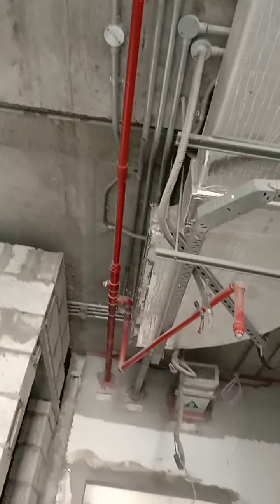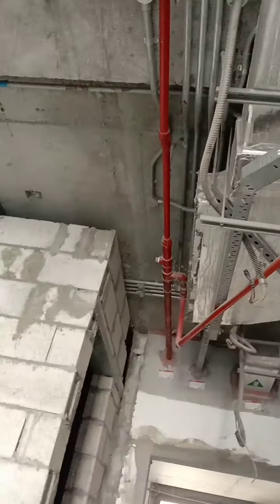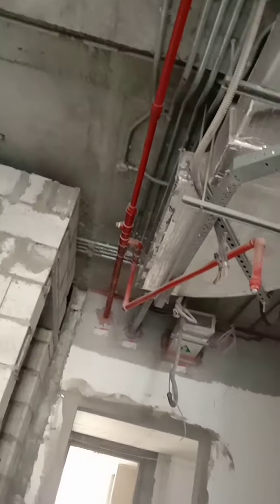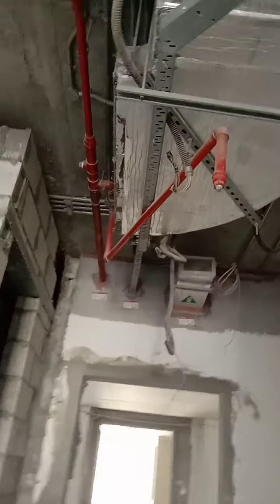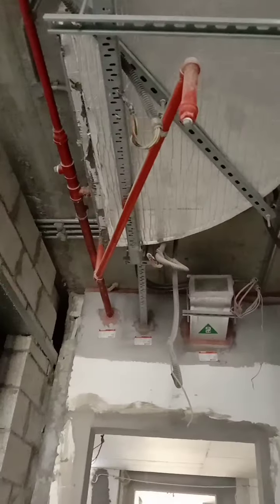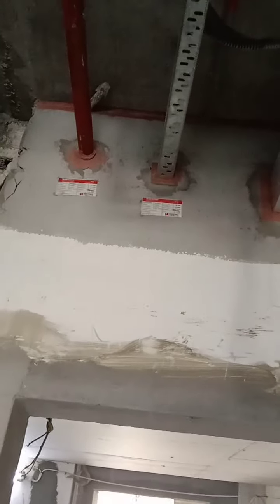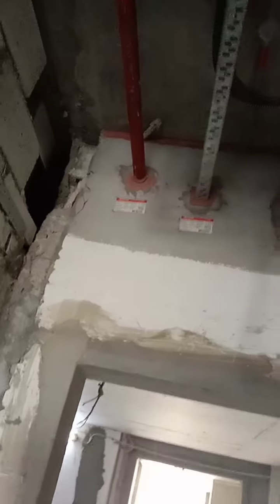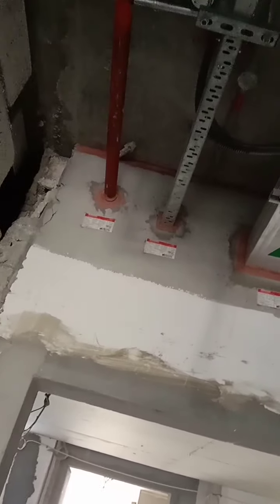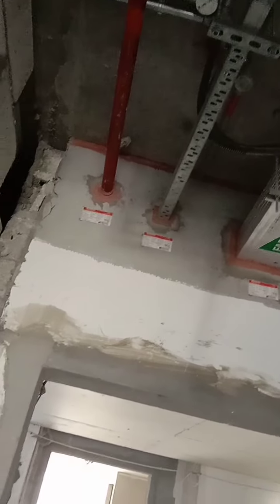When we have a penetration, which is leading from one room to another, crossing a block wall, we have to ensure that we provide sealants for these different locations. As you can see, I'll give you a quick view of it. We have fire sealant which is installed right here, but we have to know which kind of wall this is. So this wall is a fire rated wall, so we have non-fire rated walls too.